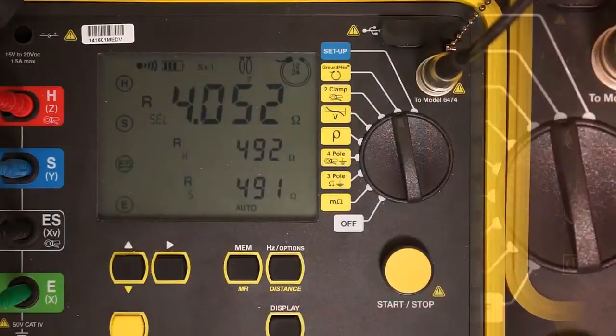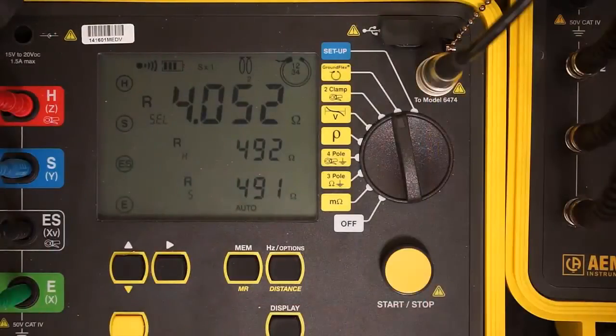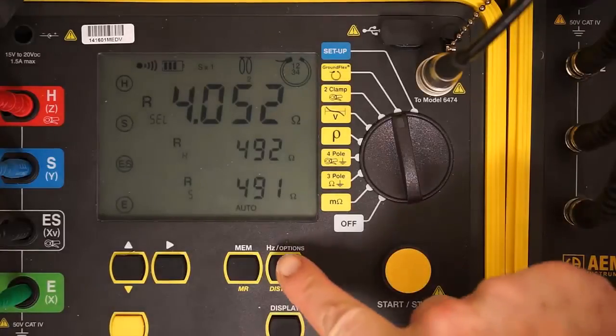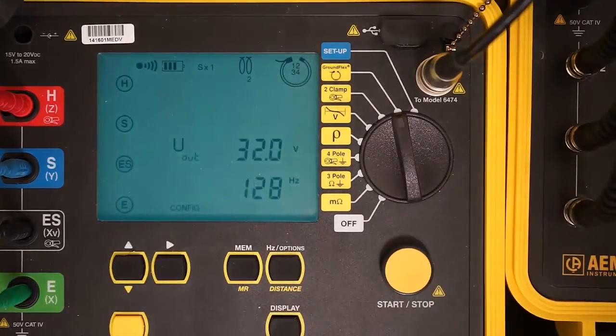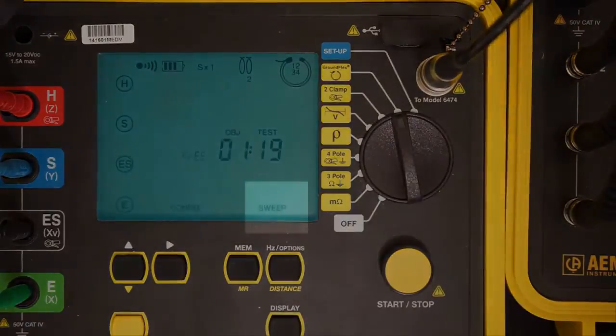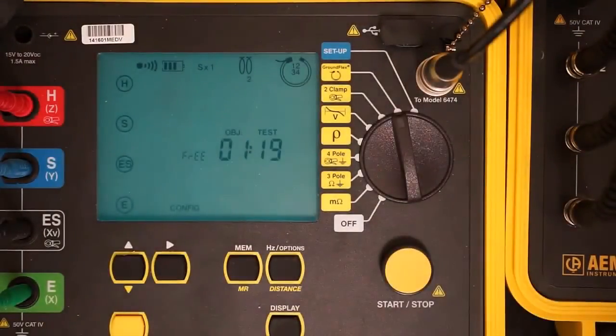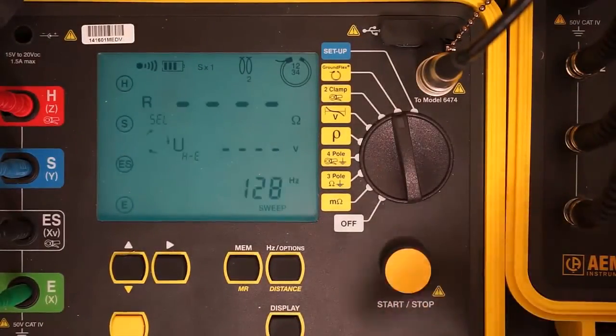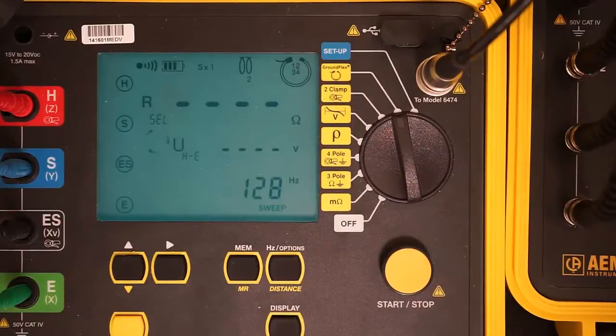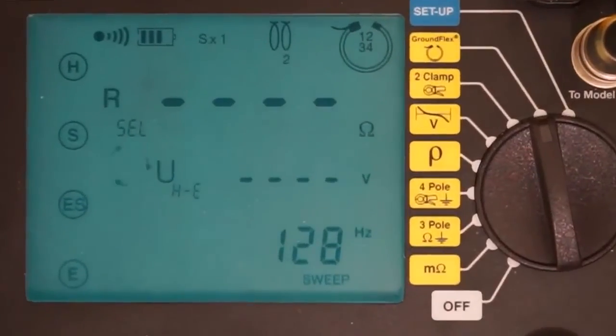We will now perform a sweep test. As noted earlier, our initial test was at 128 Hz. In the sweep test, a range of frequencies will be used, from 41 Hz up to 5078 Hz. To set up a sweep test, press the button labeled HZ Options. Then press the right arrow button until the word Sweep appears in the display. To start the test, press the Start-Stop button once. Unlike the earlier test, you do not need to hold the button down until the instrument beeps a second time.